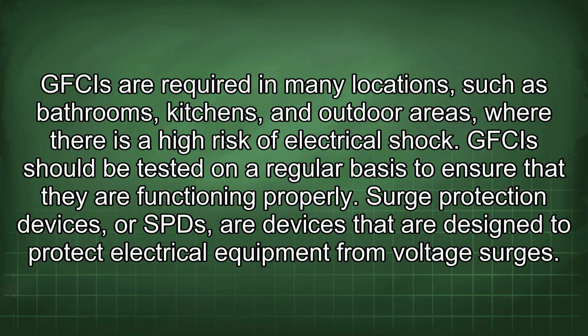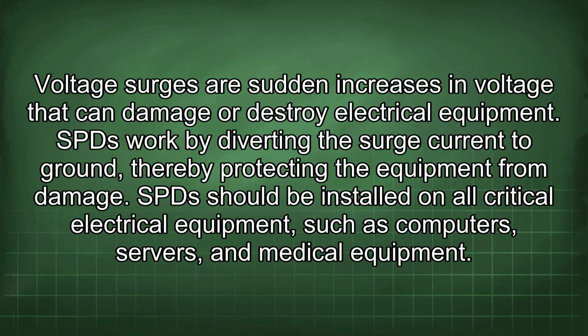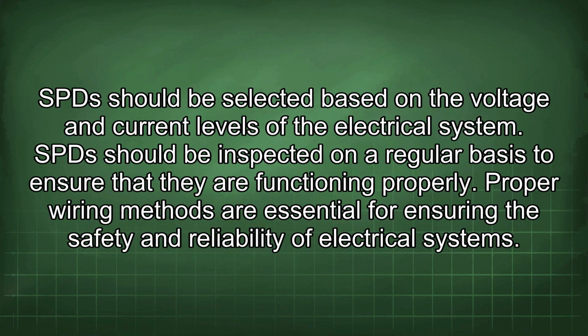Surge protection devices, or SPDs, are devices that are designed to protect electrical equipment from voltage surges. Voltage surges are sudden increases in voltage that can damage or destroy electrical equipment. SPDs work by diverting the surge current to ground, thereby protecting the equipment from damage. SPDs should be installed on all critical electrical equipment, such as computers, servers, and medical equipment. SPDs should be selected based on the voltage and current levels of the electrical system. SPDs should be inspected on a regular basis to ensure that they are functioning properly.